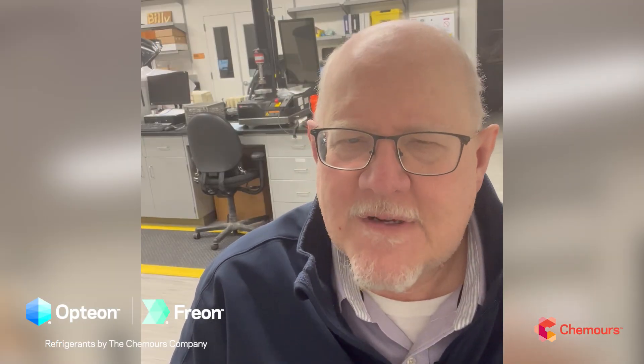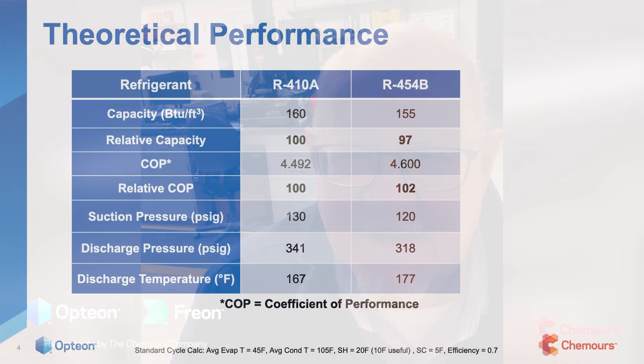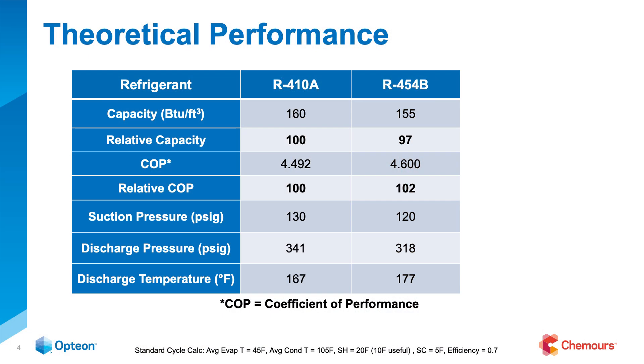One of the first things we do is a theoretical refrigeration cycle calculation analysis, and that's what you see the results of here. We basically assume a set of air conditioning evaporator and condensing temperatures with typical efficiencies, and then see what the different refrigerants do. You can see how closely the 410A and 454B match on a theoretical basis.